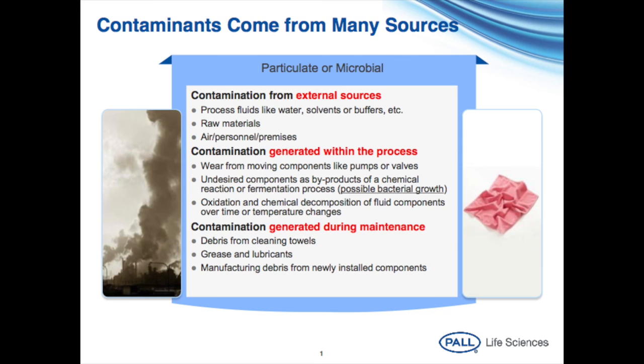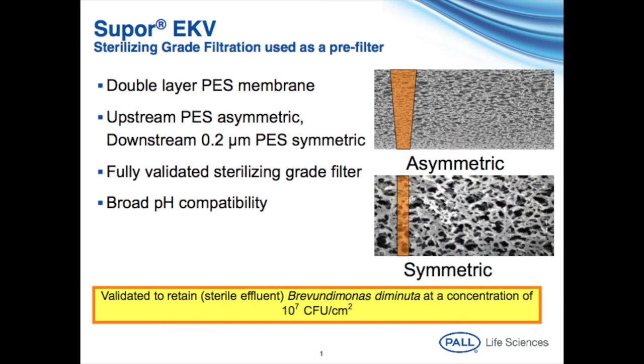A key concept we should all understand: emulsion, and especially nutrient-rich emulsion solutions, require pre-filtration directly out of microfluidizers. We learned that SUPOR-EKV as a pre-filter reduced bacterial contamination and allowed for consistency in the bacteria retention studies that followed.